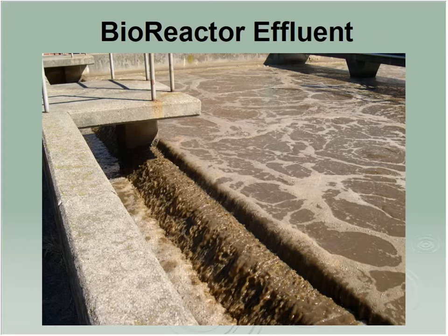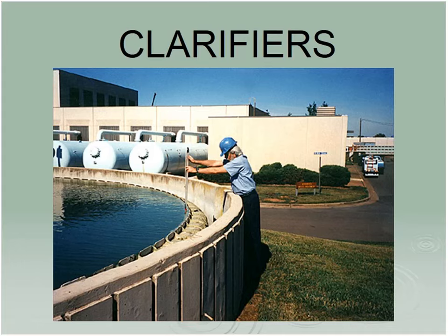So, I don't know if you recall the picture we had coming out of our primary clarifiers. Relatively clean-looking water. This is what comes out of your reactor. Difference being that population of organisms that you grow. So it comes in looking like slightly dirty water to look more like chocolate milk. You're talking 2,500 to 3,000 milligrams per liter of solids in there. Really a quarter to a third of a percent from the solids standpoint.